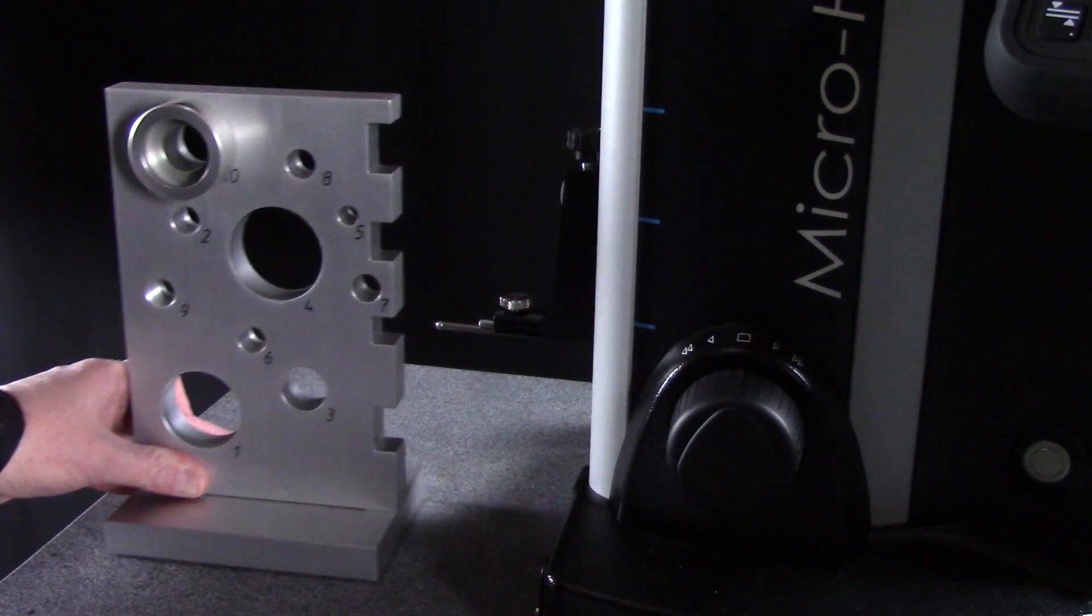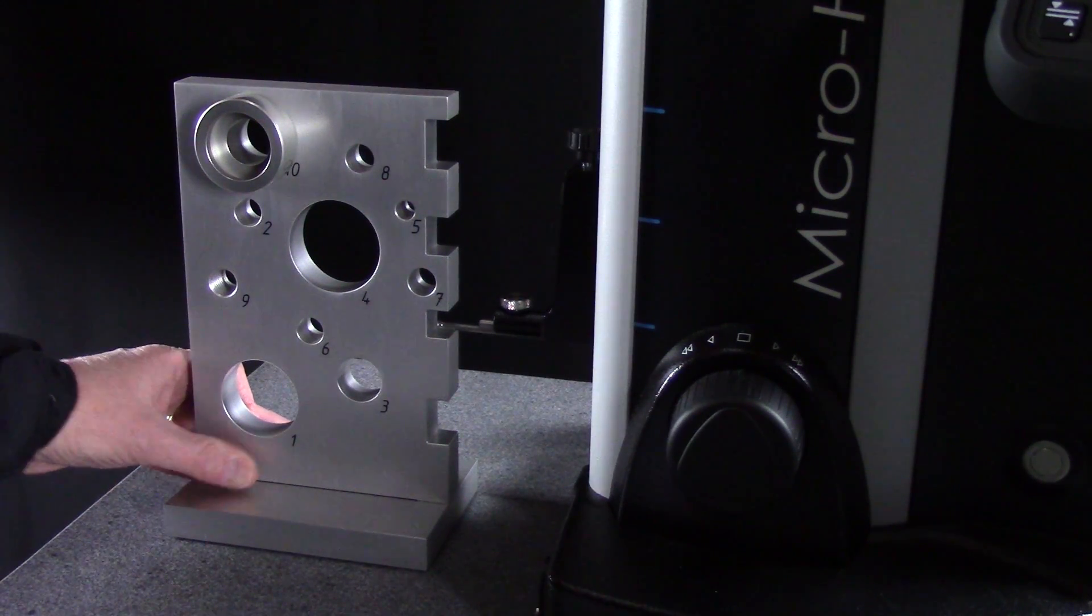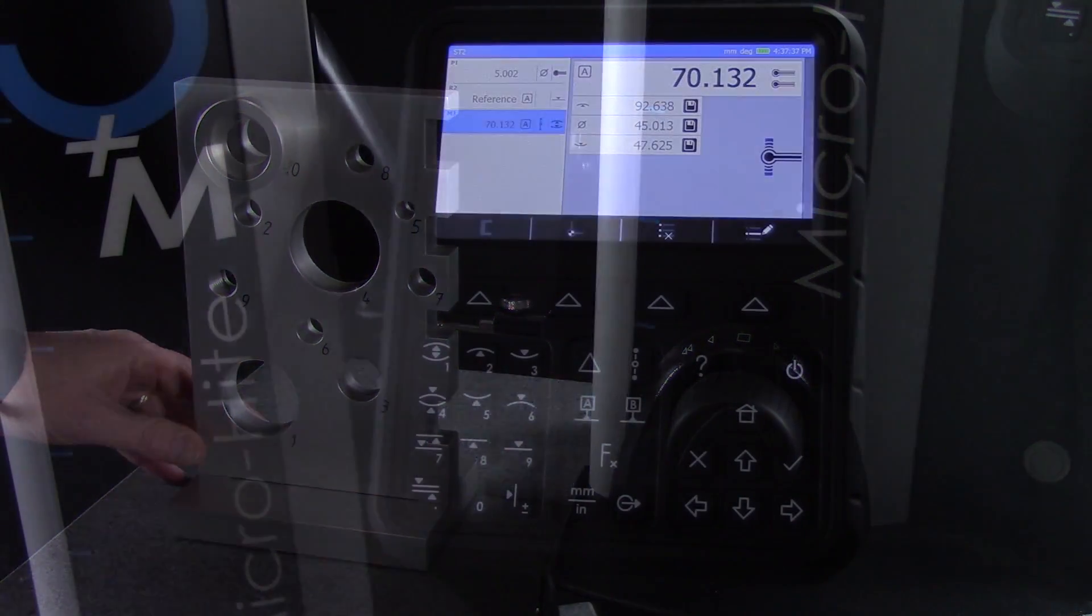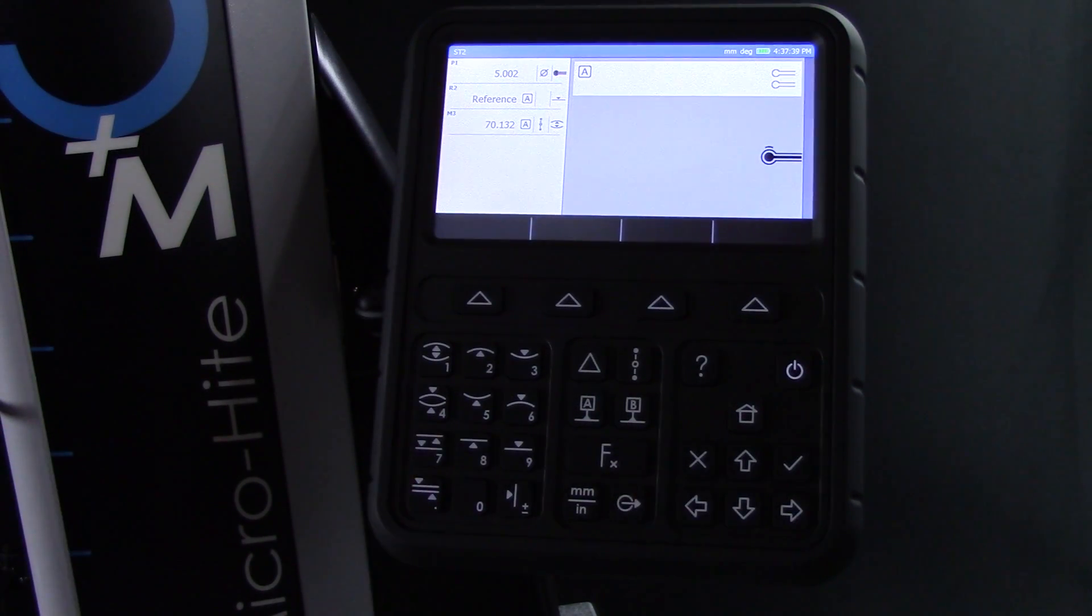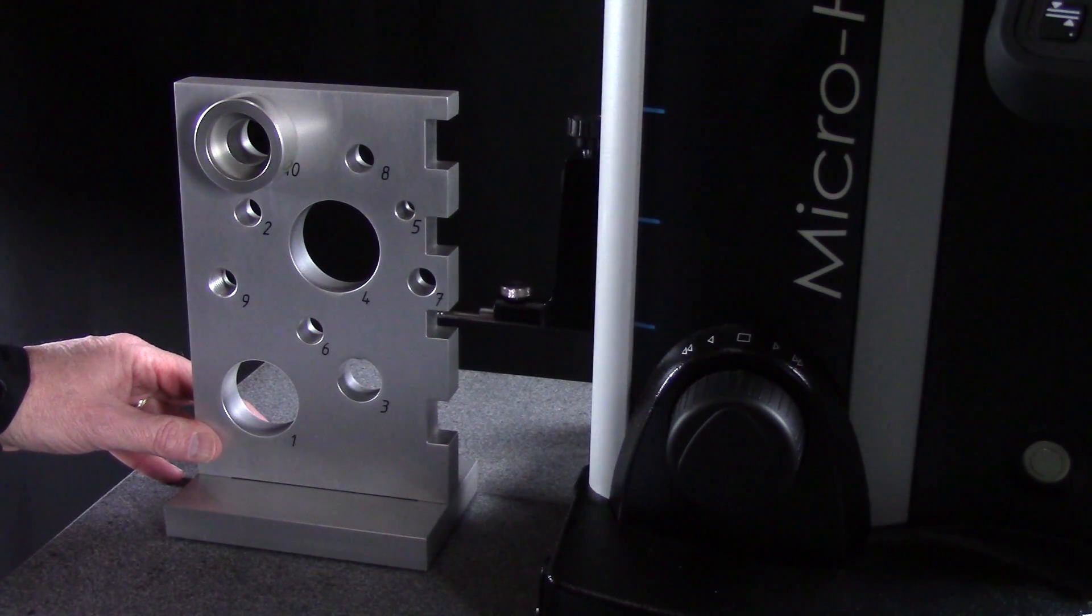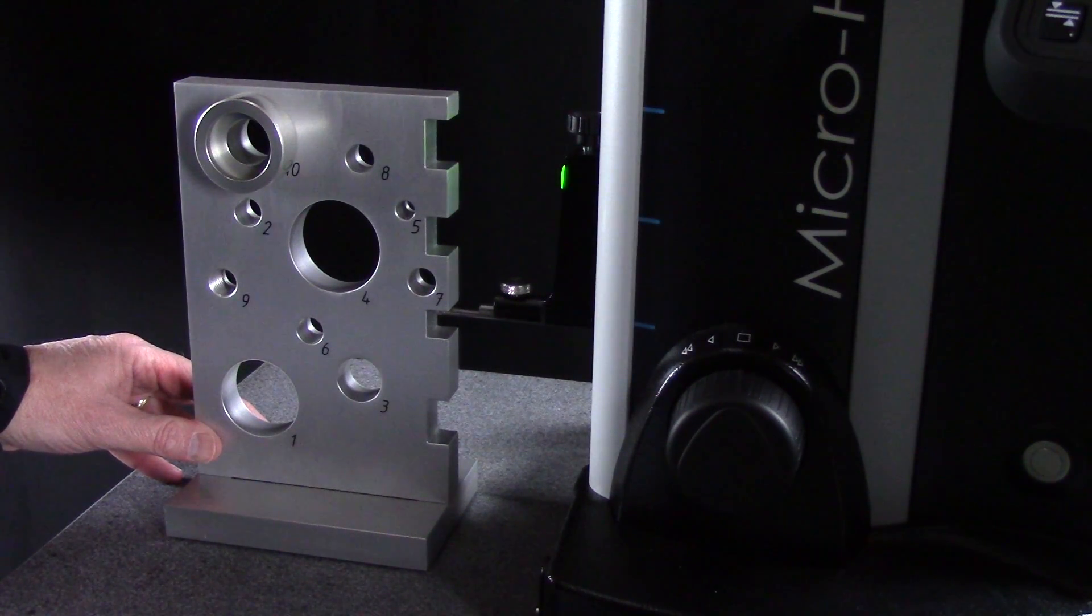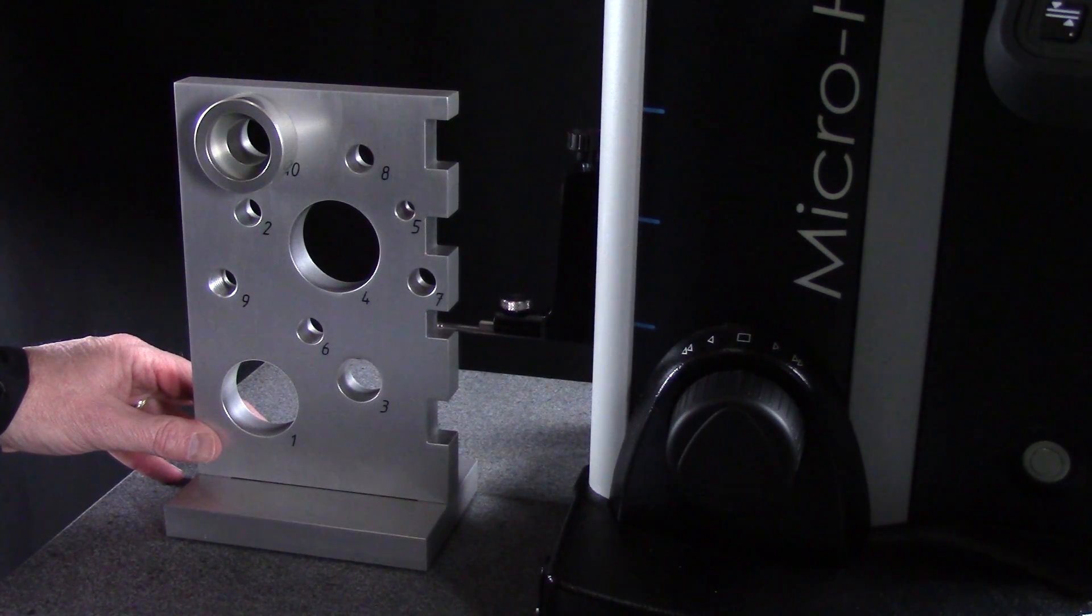Next, I'll measure this slot. With my part in position, I'll select the automatic groove measurement button on the keypad. The probe will measure the top and bottom of the slot, and the measured result will be displayed.